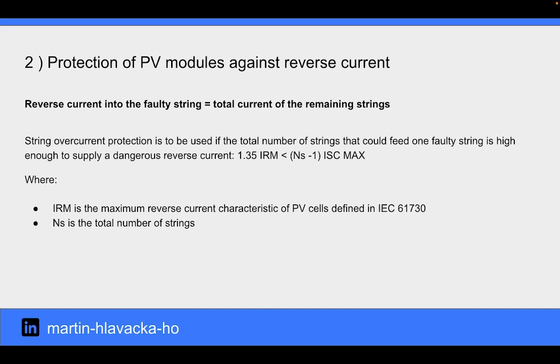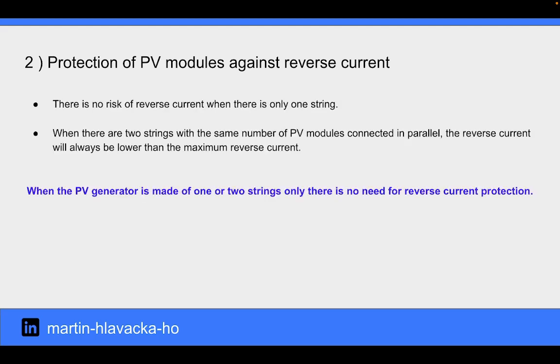String overcurrent protection is to be used if the total number of strings that could feed one faulty string is high enough to supply a dangerous reverse current. There is no risk of reverse current when there is only one string. When there are two strings with the same number of PV modules connected in parallel, the reverse current will always be lower than the maximum reverse current. So when the PV generator is made of only one or two strings, there is no need for reverse current protection.